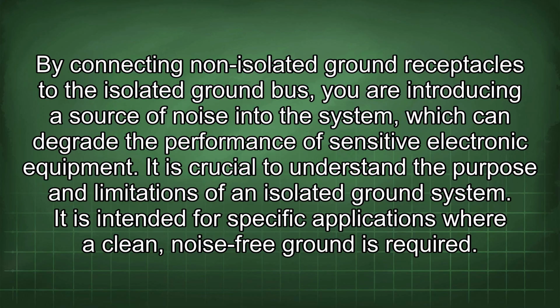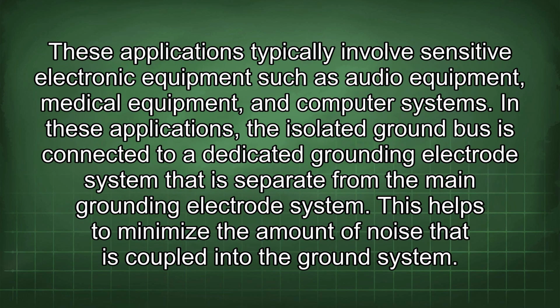It is crucial to understand the purpose and limitations of an isolated ground system. It is intended for specific applications where a clean, noise-free ground is required. These applications typically involve sensitive electronic equipment such as audio equipment, medical equipment, and computer systems. In these applications, the isolated ground bus is connected to a dedicated grounding electrode system that is separate from the main grounding electrode system. This helps to minimize the amount of noise that is coupled into the ground system.